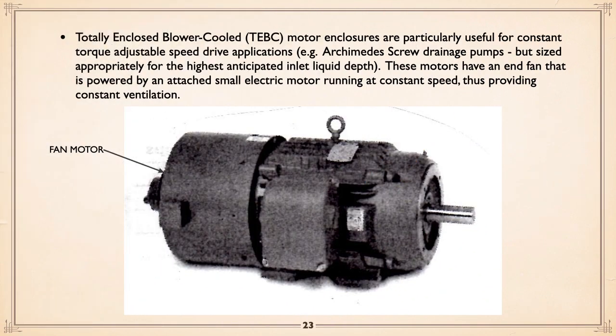Where it poses a problem is if you're driving something where it's constant torque or close to it. In other words, not a centrifugal pump, but a positive displacement pump, which is basically what an Archimedes screw pump is. And I mentioned, as we were talking before, it needs to be appropriately powered for the highest anticipated inlet liquid depth. Now, because you want cooling, because the motor is going to stay quite hot since the load is quite high, what you do is you have a separate constant speed fan motor. And if you look at the back of that motor, there's a little tiny smaller motor which is driving the fan only, giving you constant ventilation.